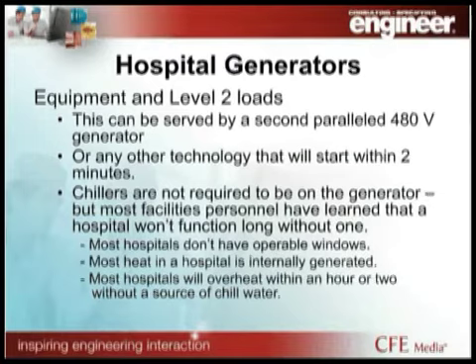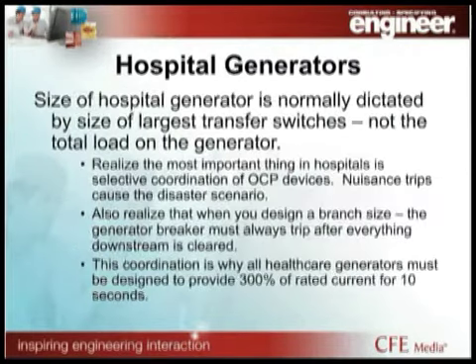Another evolving need within the hospital design community is chillers on emergency power. This seems obvious to a lot of us, but a hospital facility has a lot of internally generated heat. Most hospitals don't have operable windows, and chillers are not required by code to be on the generator. So more and more we push to recommend to our clients that the chillers be connected to the generator, even if they aren't part of the primary function to be on that generator power. And we're going to see another reason to put all chillers on generators later.